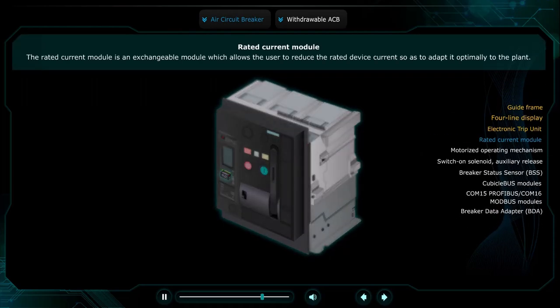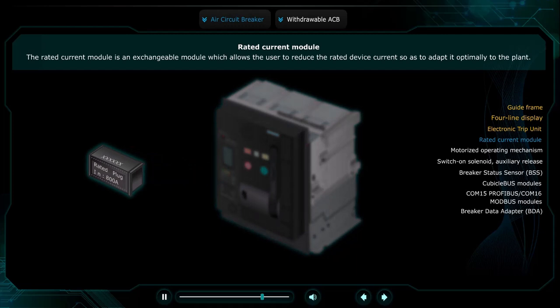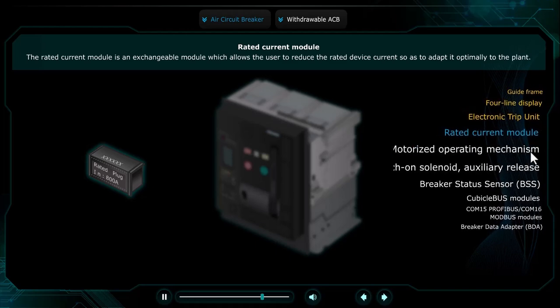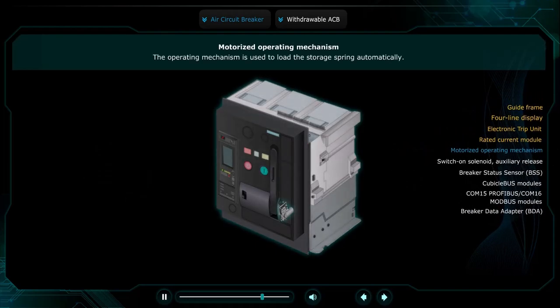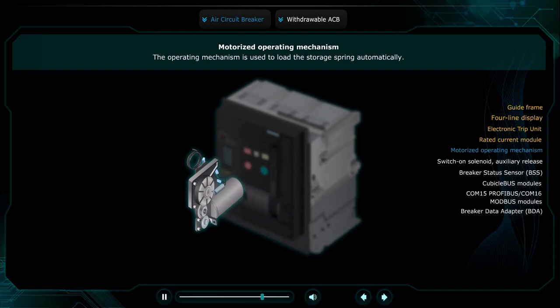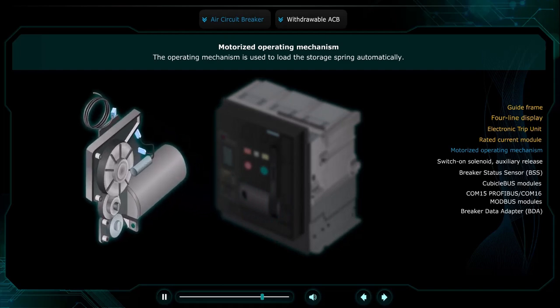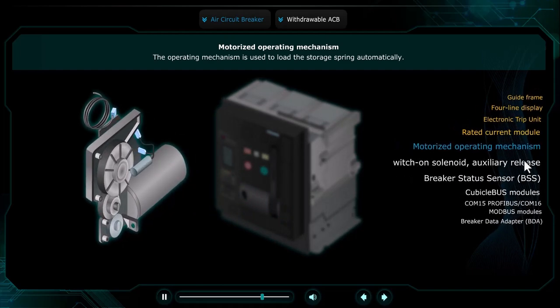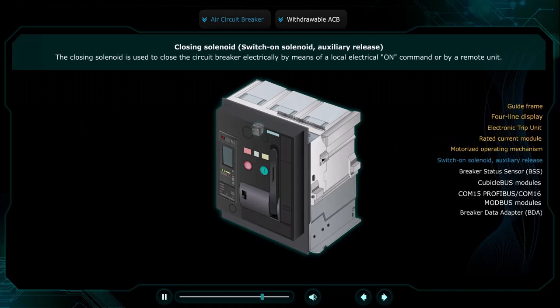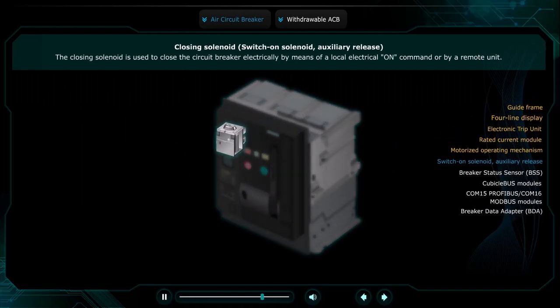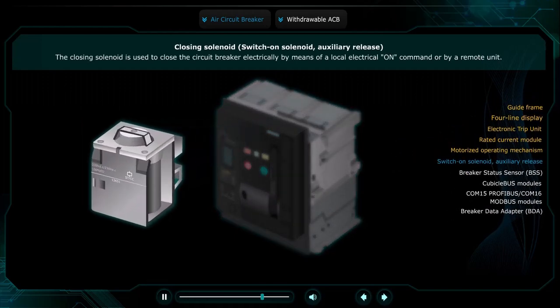The rated current module is an exchangeable module which allows the user to reduce the rated device current so as to adapt it optimally to the plant. The operating mechanism is used to load the storage spring automatically. The closing solenoid is used to close the circuit breaker electrically by means of a local electric on command or by a remote unit.